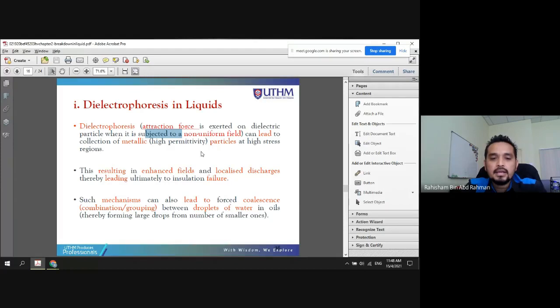Once the metallic particles accumulate at one area, this leads to an enhanced electric field, which becomes greater and triggers localized discharge at that particular place. It's not a breakdown, just discharge, but if the discharge activity occurs continuously over a long time, it will degrade the dielectric material's function and reduce its dielectric strength compared to the original.